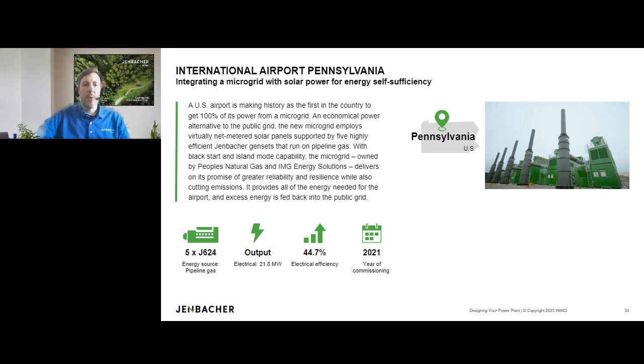So not only do they have the chance to run these in grid parallel as needed, but they can also go completely island mode. If there's an outage—and obviously an airport can never have an outage in terms of power—they can start these units, black start, and island the whole airport, which really provides a very resilient solution to this customer. It's a testament to our engines as well, since they selected this technology to be that reliable source of energy in case the grid is not.